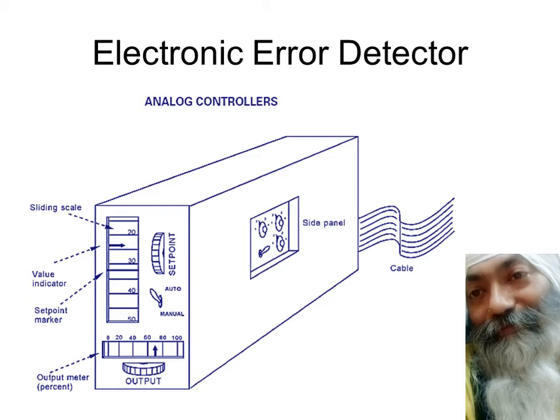What is shown here is an analog controller. As we see on the panels, the set point of an analog controller is normally adjusted with the help of a thumb wheel. This set point can be in the form of a pointer, and whatever the value is, it's indicated by a value indicator. You can have a sliding scale with a set point marker — right now it's set to around 33 or 34 degrees — and the current value is shown moving towards the set point.